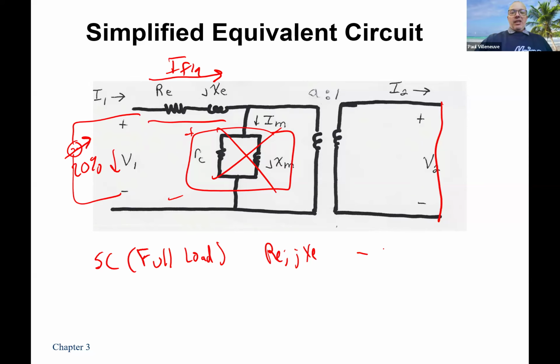So my short circuit test, here's what I actually have left over. So what would you measure? Forget it's a transformer. I gave you a lab assignment, a homework assignment. Go ahead and tell me what you need to measure. You can go to the lab and do whatever you want. But inside of a box, I have RE and JXE. What kind of a set of parameters would you measure? Would you stick a multimeter on it and measure RE and JXE? Hope not, because we just talked about the fact that you have leakages and you have I squared R losses, and those aren't going to be all that useful to measure that. So what would you do?